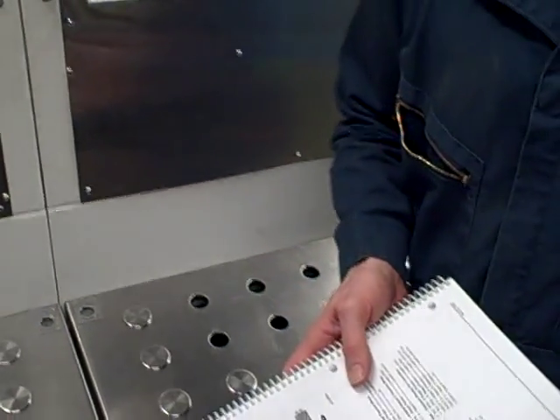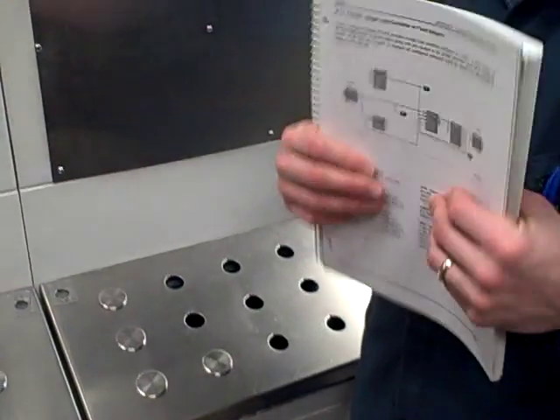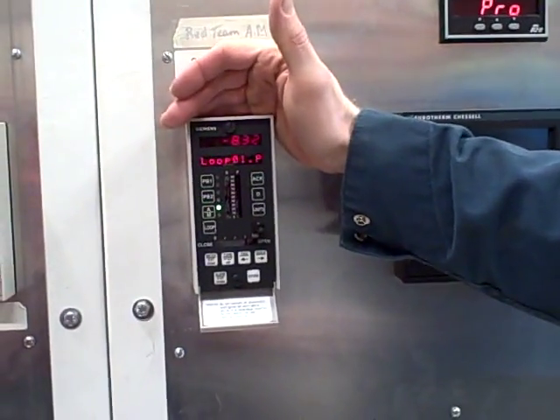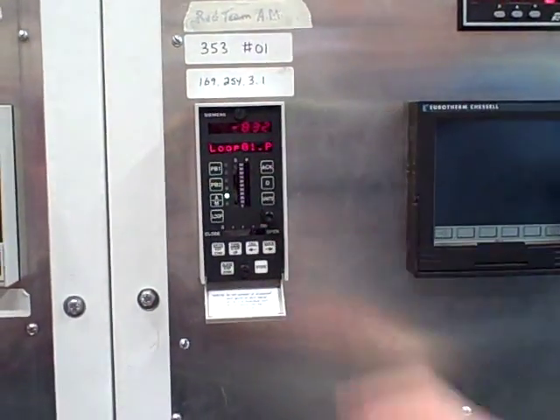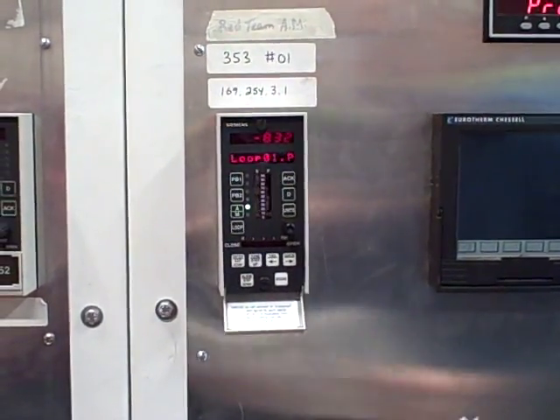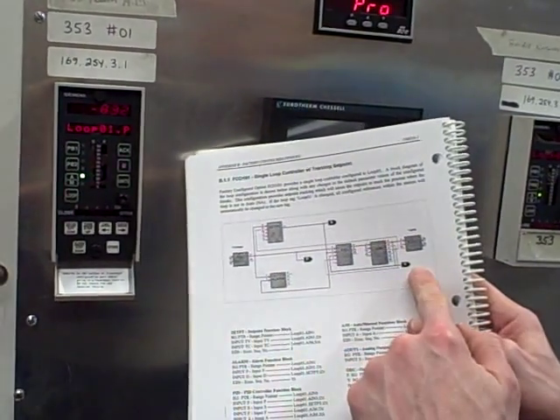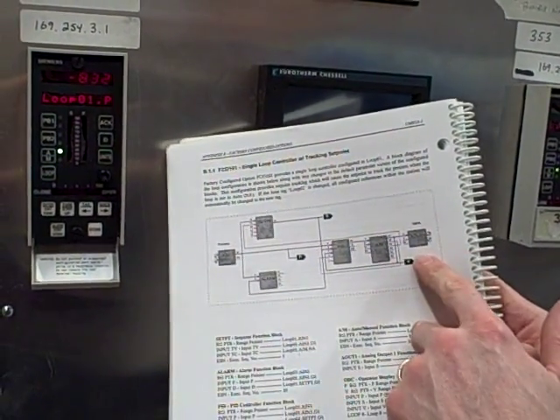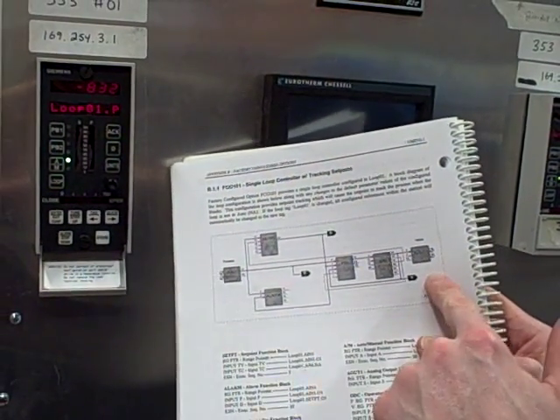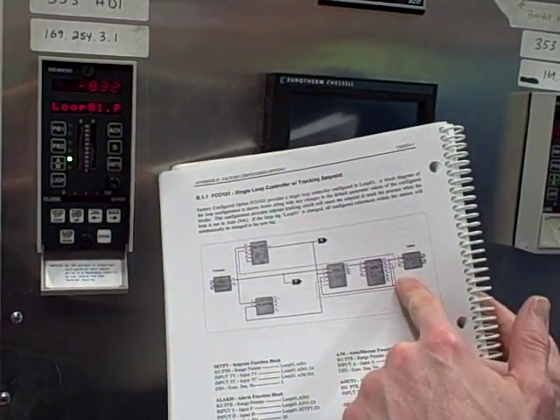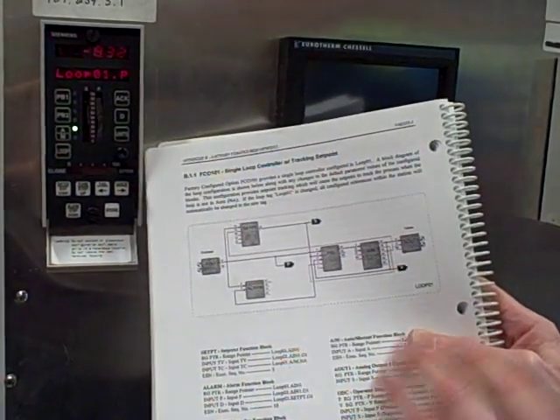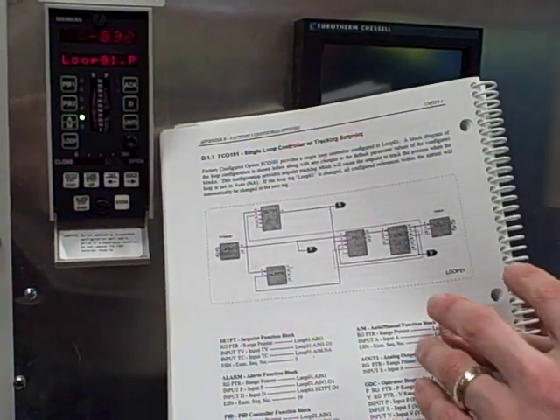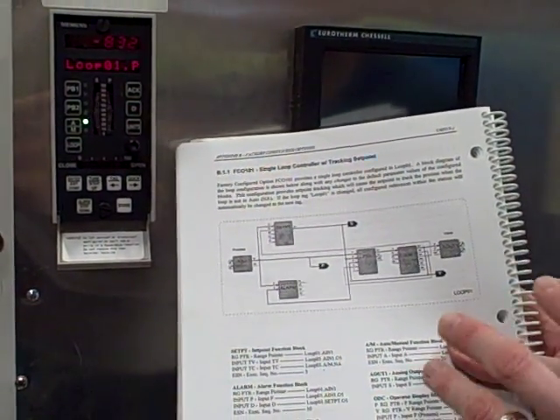What we're going to do here is set double or dual analog outputs on a Siemens Model 353 loop controller. Presently, this is set up for its factory configured option 101, which shows a single loop control, very basic. We want to add a second analog output block in this function block program so that we will have two active analog outputs, both of them 4 to 20 milliamps, both driving the same signals to two different valves, which we will then split range.